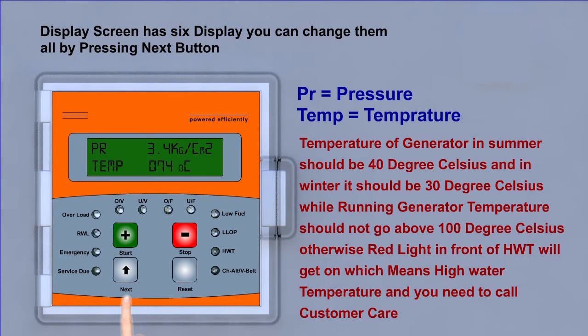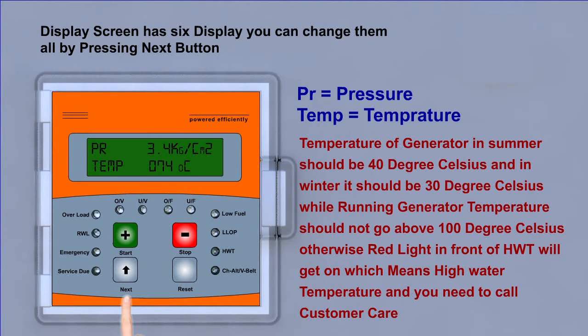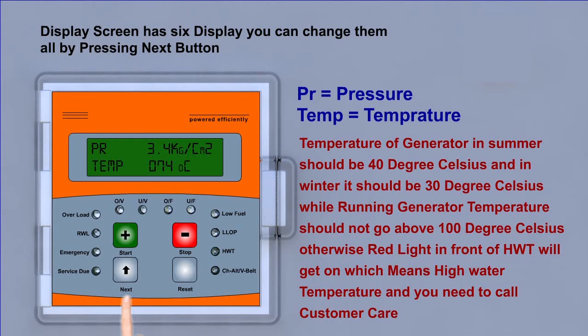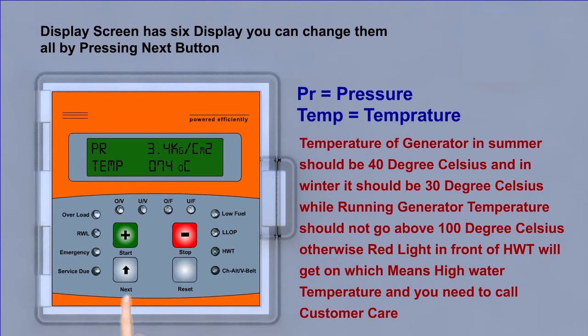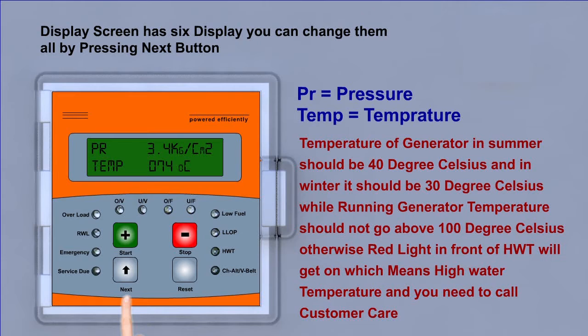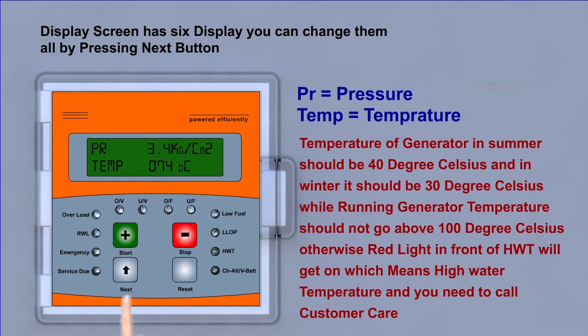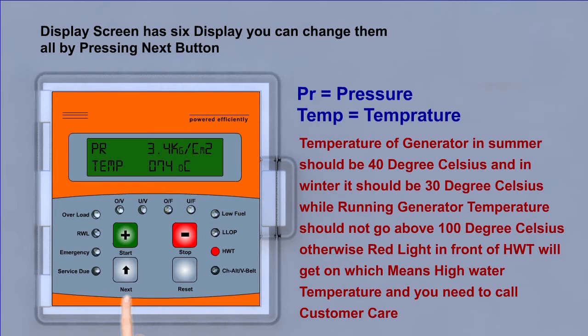Temperature of generator in summer should be 40 degree Celsius and in winter it should be 30 degree Celsius. While running generator, temperature should not go above 100 degree Celsius. Otherwise, red light in front of HWT will get on, which means high water temperature.